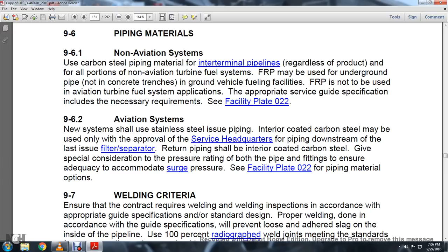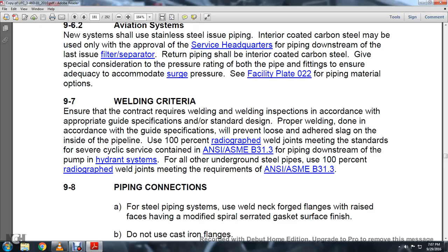Proper welding done in accordance with the guide specifications will prevent loose adhered slag on the inside of the pipeline. Use 100% radiographed welded joints meeting the standard of the ANSI ASME B31.3 for piping downstream of the hydrant system.